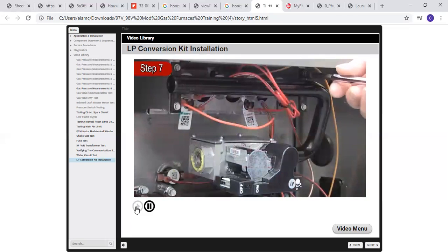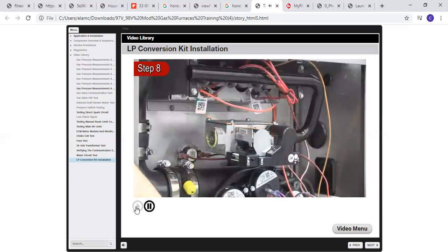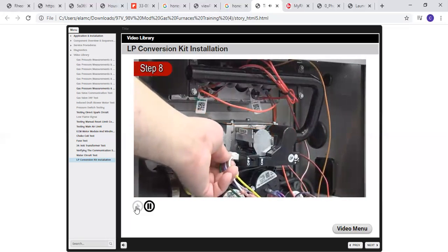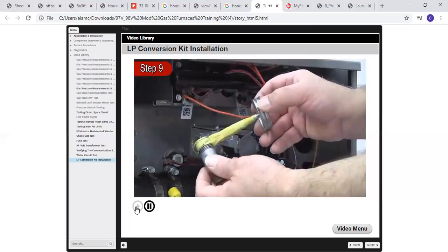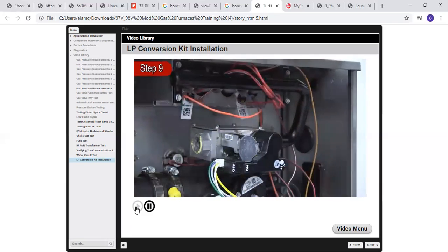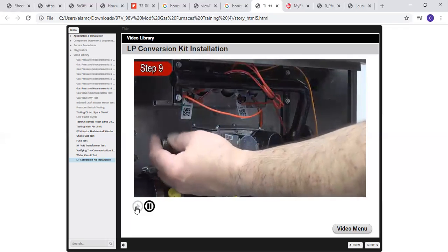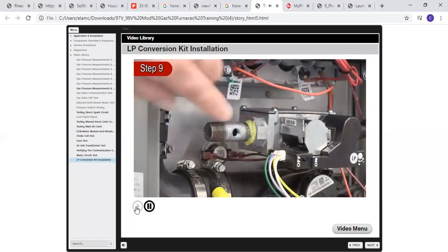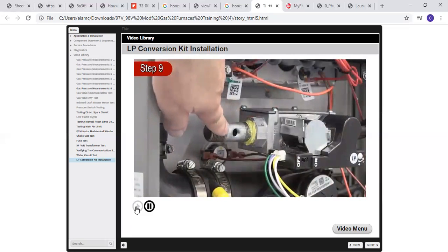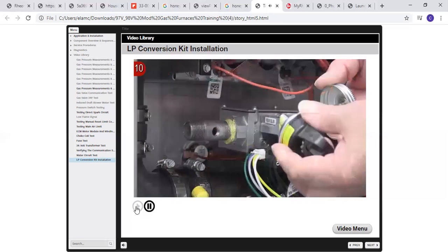Step 7. Reinstall the manifold assembly by reversing the removal process. Step 8. Plug the wires into the gas valve. Step 9. Install the tapped gas nipple supplied with the kit into the inlet of the gas valve. Be sure to apply pipe dope or Teflon tape. After tightening the gas nipple, the tapped hole in the nipple should be in the horizontal position.